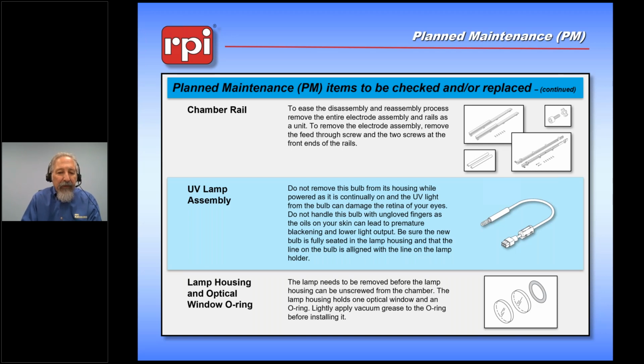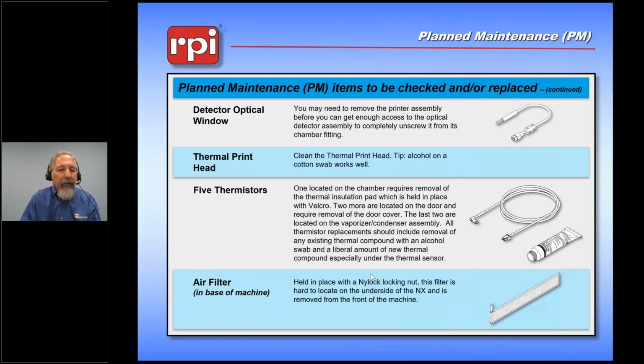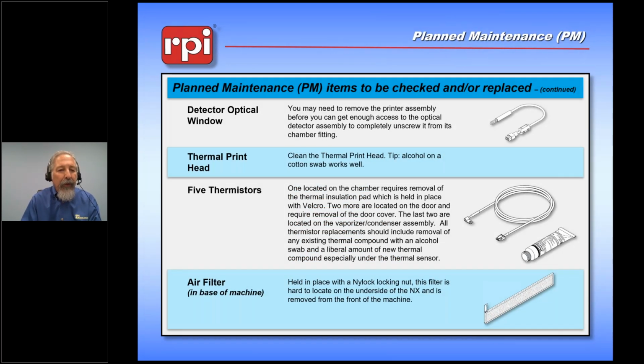We have a set of optical windows included in the planned maintenance kits. One of them goes in the top below the UV lamp assembly. Make sure that it's seated properly and the O-ring is in properly. The second optical window is located in the bottom of the chamber and just fits into an opening. As I mentioned earlier, there is also a third window, part of the detector optical system.